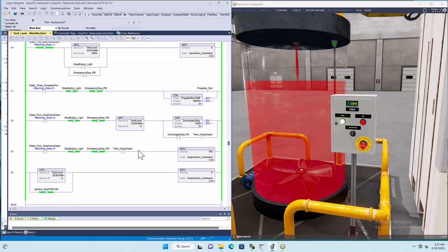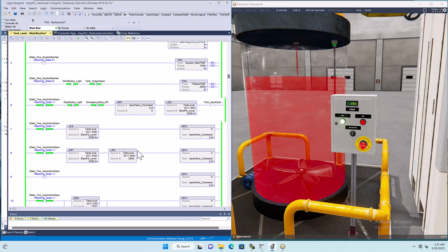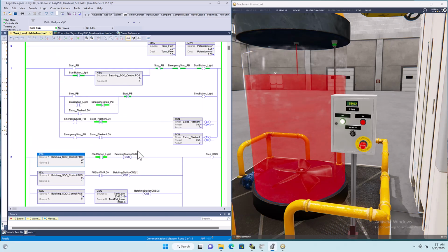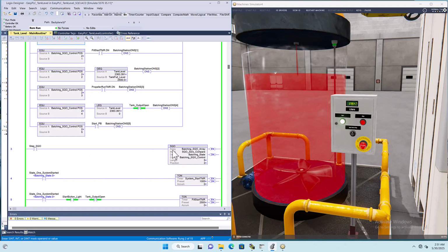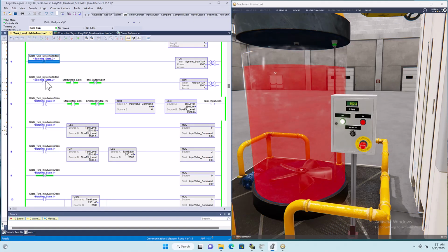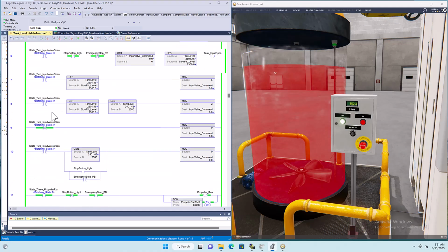And if you compare this to the ladder logic version of what I had, it's very similar. It's not very hard to read, it's not very confusing. The only thing about it is it's using the sequencer. And as long as you know what the sequencer is doing, in the batch array we use binary coded decimal. So we use 1, 2, 4, 8, 16, 32, 64, 128. Obviously, we only have 5 steps, so we only have the bits right here that we're currently using, and I did alias those bits as you've seen in the last video.